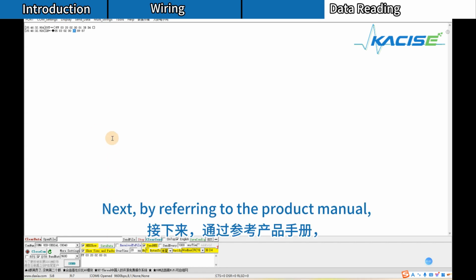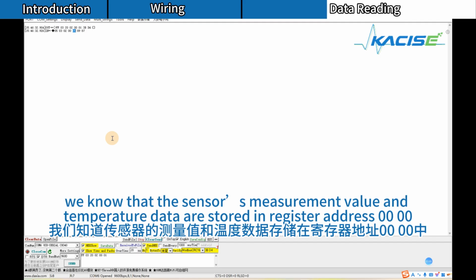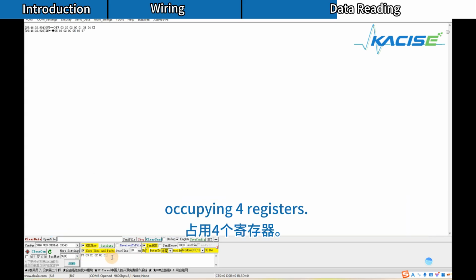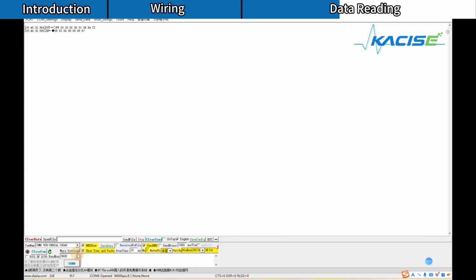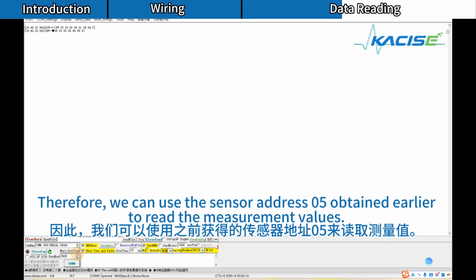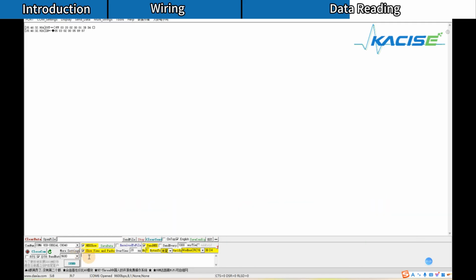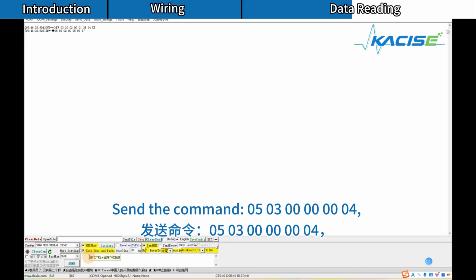Next, by referring to the product manual, we know that the sensor's measurement value and temperature data are stored in register address 00 00, occupying 4 registers. Therefore, we can use the sensor address 05 obtained earlier to read the measurement values. Send the command 0503000004.